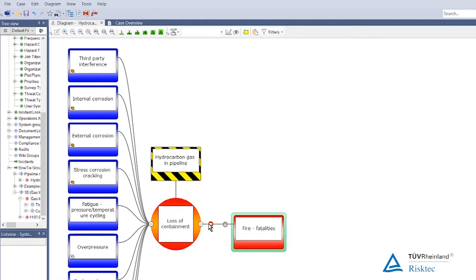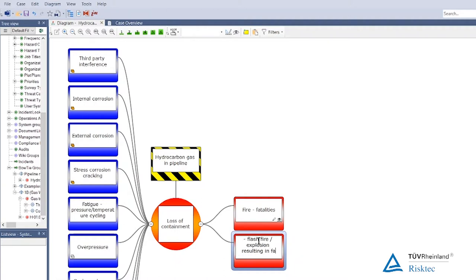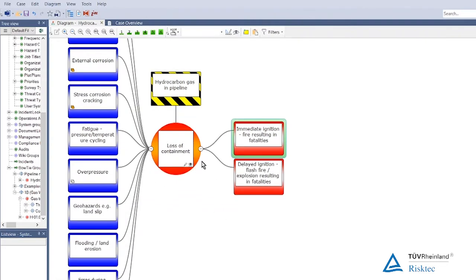For completeness, we could put in a second consequence of a delayed ignition resulting in a flash fire, fireball, or explosion. We also need to consider whether pollution events or unignited releases are an issue — for natural gas, that's not going to be a major concern. As duty holders, we're going to be primarily worried about the safety impacts.